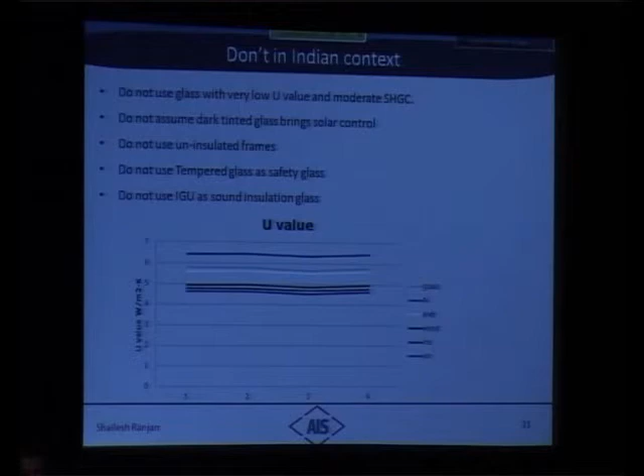Now the don'ts. Do not use glass with a very low U value and moderate solar factor, because it is a kind of glass which is not applicable for the Indian kind of climate. We should not assume that a dark tint glass is better. Normally people think that if we put kala glass, it will perform better. It is not. It is the coating which is done on the glass which performs, not the tint of the glass.